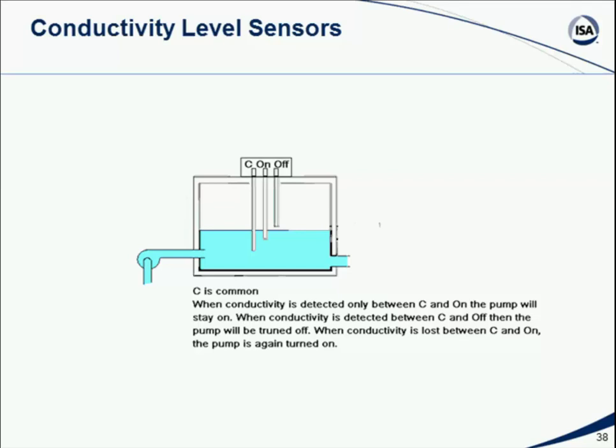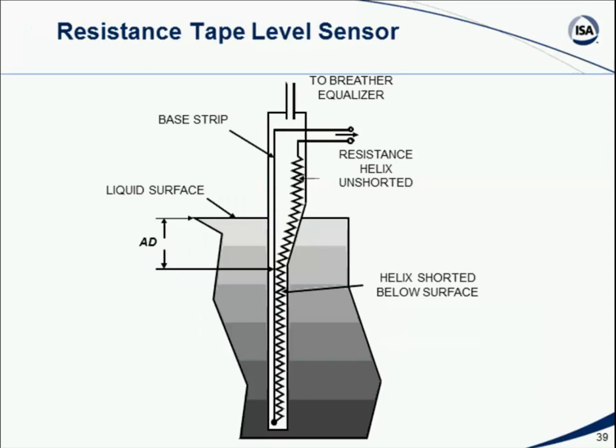We care if the tank drops below a certain level. We care if the tank is getting above a certain level, but in between we probably don't care. So in that case, using conductivity sensors like this with these simple probes might be a perfectly applicable way of measuring the level in the tank. But again, those are point measurements.